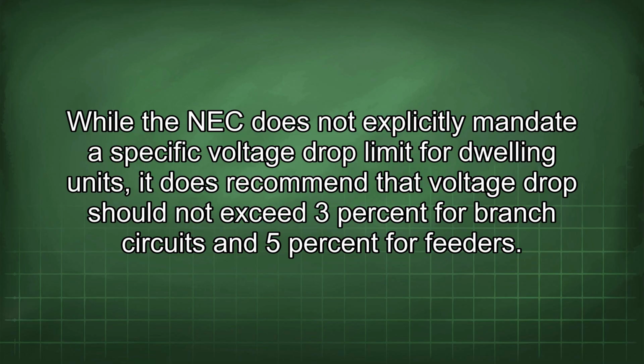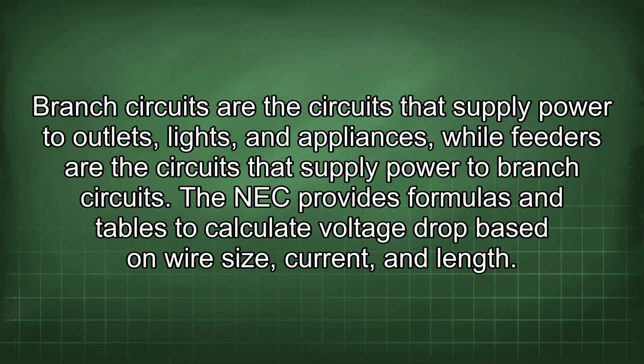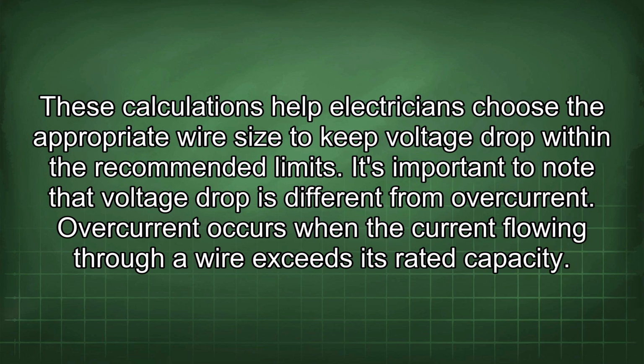While the NEC does not explicitly mandate a specific voltage drop limit for dwelling units, it does recommend that voltage drop should not exceed 3% for branch circuits and 5% for feeders. Branch circuits are the circuits that supply power to outlets, lights, and appliances, while feeders are the circuits that supply power to branch circuits. The NEC provides formulas and tables to calculate voltage drop based on wire size, current, and length. These calculations help electricians choose the appropriate wire size to keep voltage drop within the recommended limits.